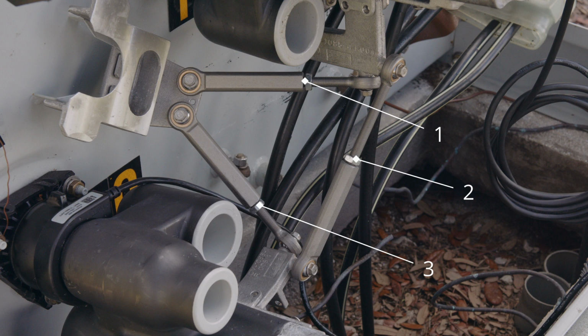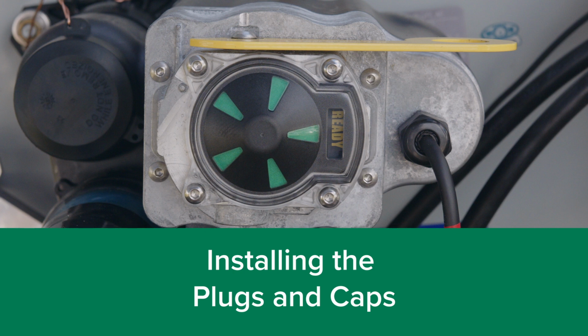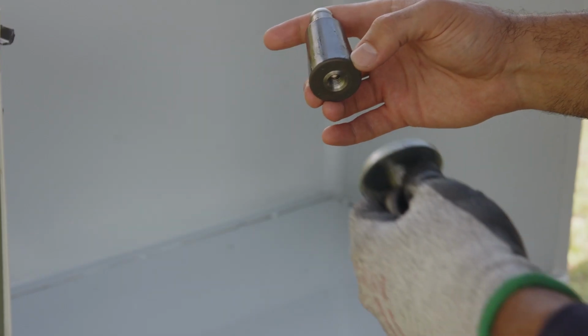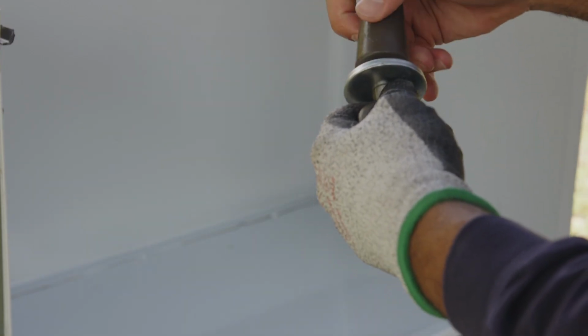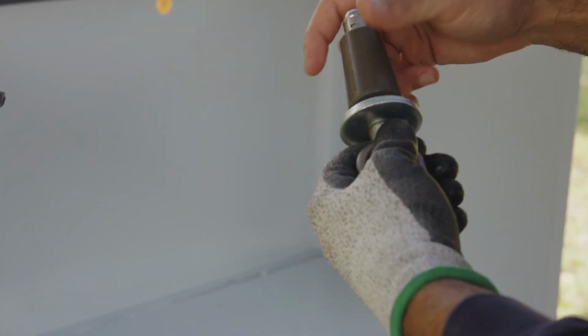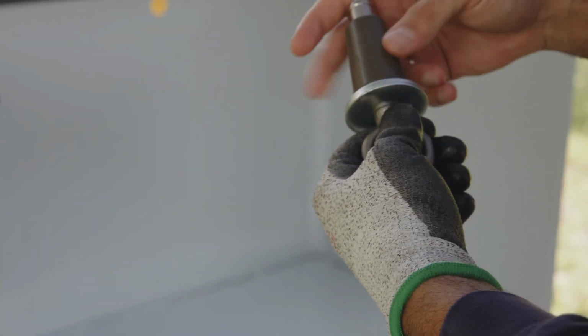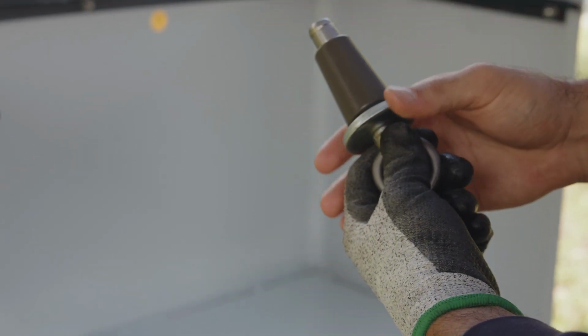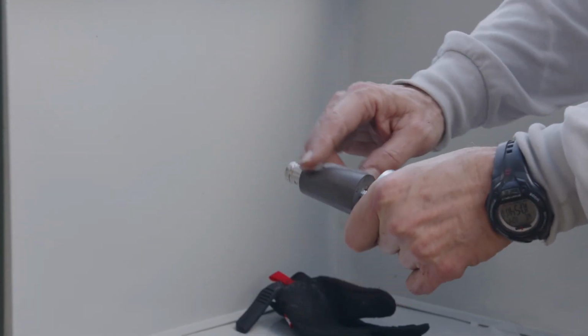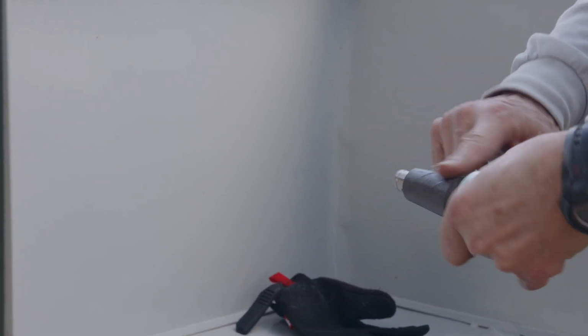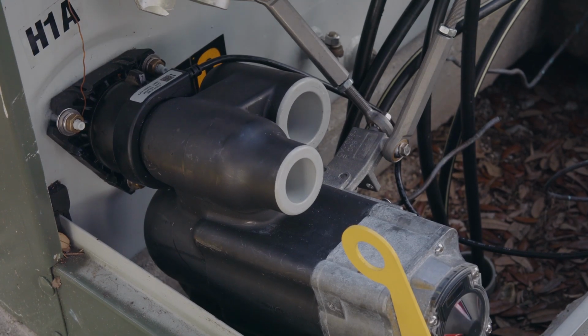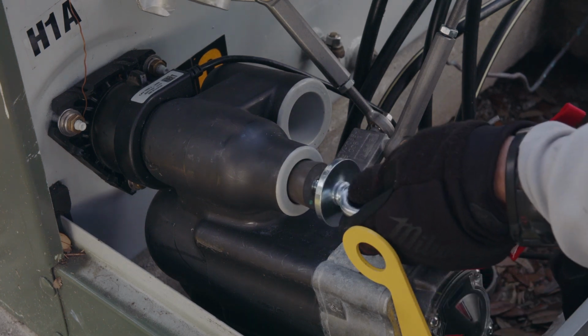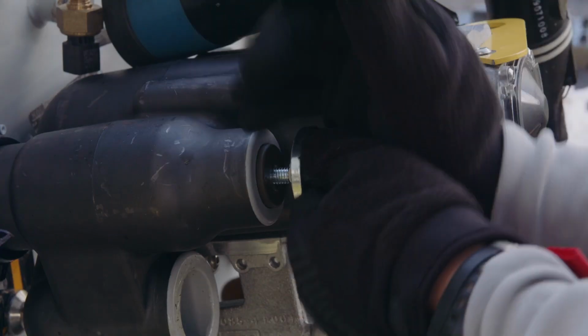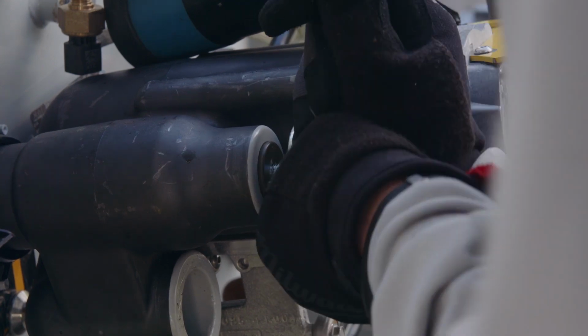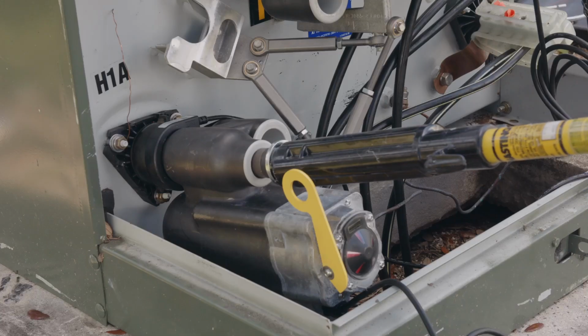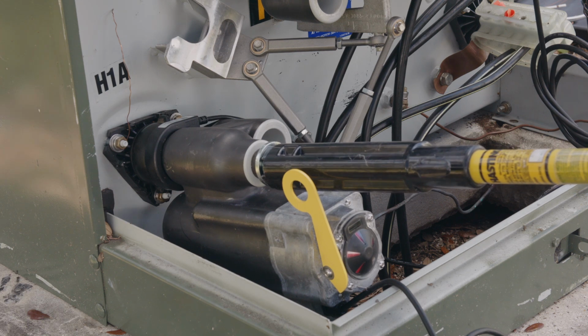Follow these steps to install the plugs and caps. Step 1. Attach the plug install removal tool to the end of the plug. The tool will not screw all the way flush to the plug. Step 2. Grease the taper of the plug for the H1A bushing well interrupter with silicone lubricant. Step 3. Install the plug in the H1A bushing well interrupter. This takes substantial force to snap into place and may be easier to do with a shotgun stick or a hook stick fitted with a distribution prong.